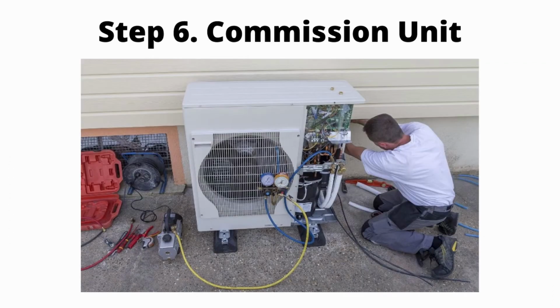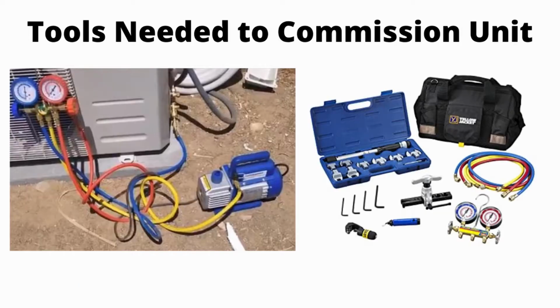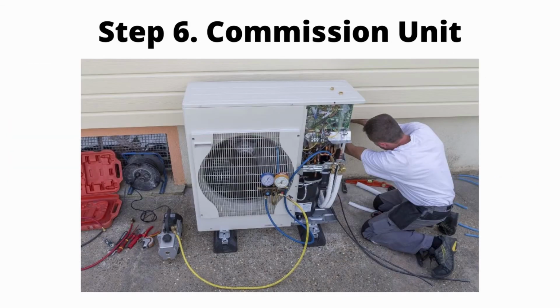Depending upon the unit that you purchase, you may be instructed to test the copper line set for leaks. We typically use a nitrogen test with a special pump. There is special equipment for testing the leaks as well as equipment for measuring the refrigerant levels. Once you have determined that there are no leaks, you will need to release the refrigerant into the system. The next step is to turn on the power to the disconnect box and test the unit. If you are successful, your unit should be able to work.